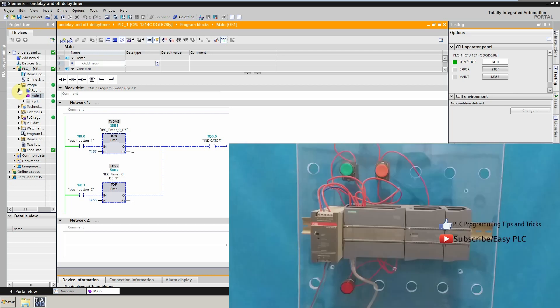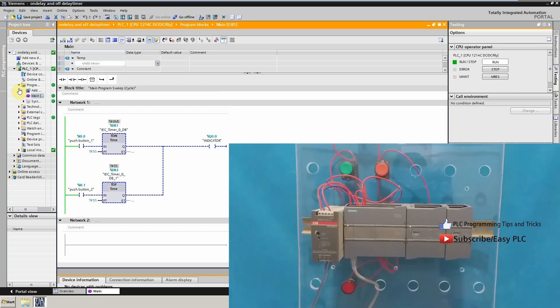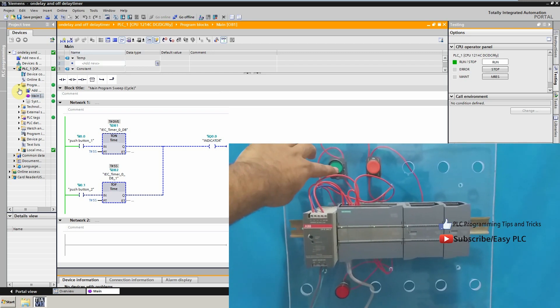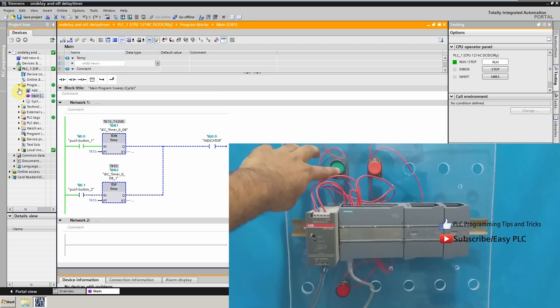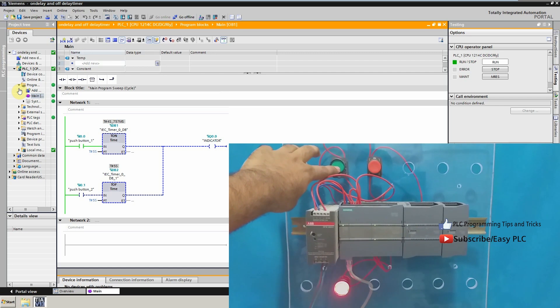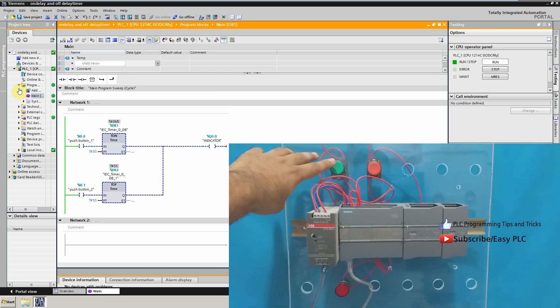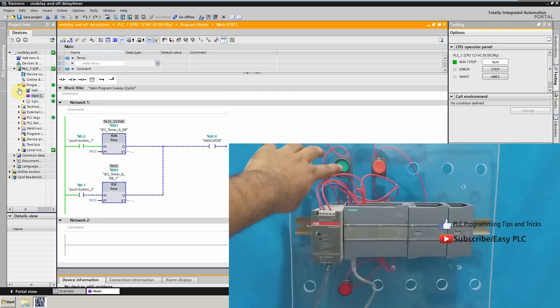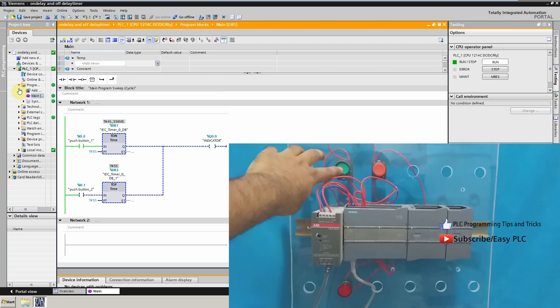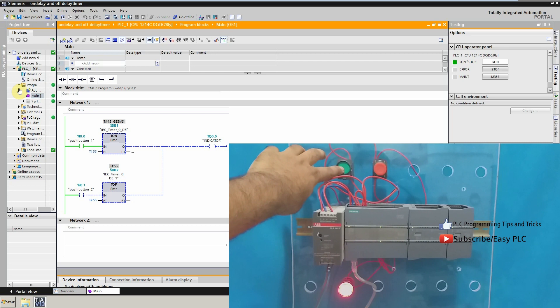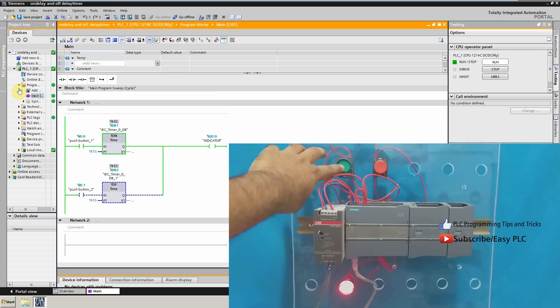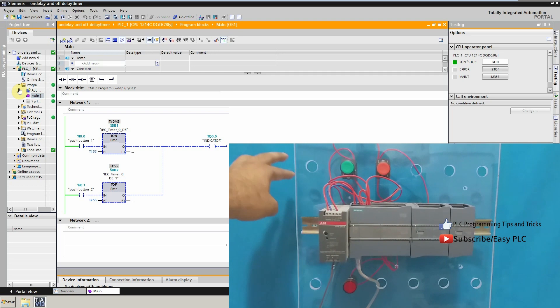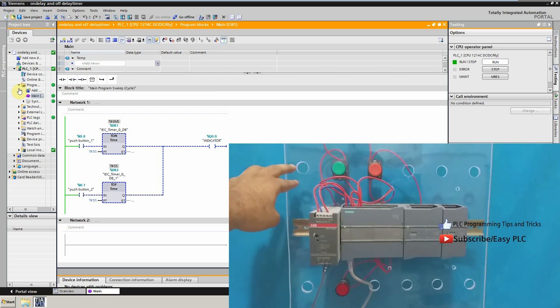As you can see, when we press the green push button which is I0.0, the ON delay timer starts. When five seconds are over, output Q0.0 turns on. When we release the push button, output Q0.0 goes off. Now we will see how the OFF delay timer works.